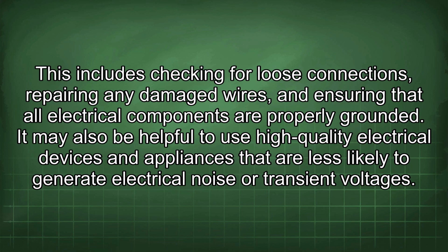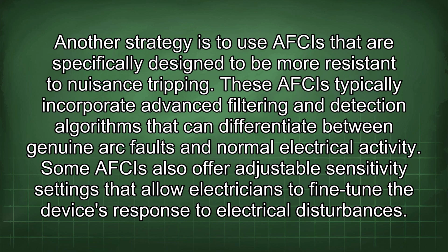It may also be helpful to use high-quality electrical devices and appliances that are less likely to generate electrical noise or transient voltages. Another strategy is to use AFCIs that are specifically designed to be more resistant to nuisance tripping. These AFCIs typically incorporate advanced filtering and detection algorithms that can differentiate between genuine arc faults and normal electrical activity. Some AFCIs also offer adjustable sensitivity settings that allow electricians to fine-tune the device's response to electrical disturbances.